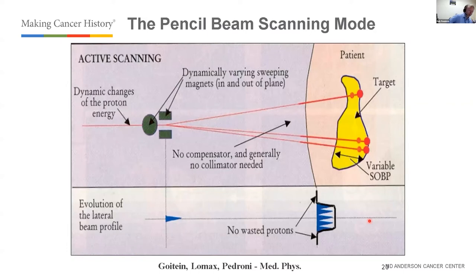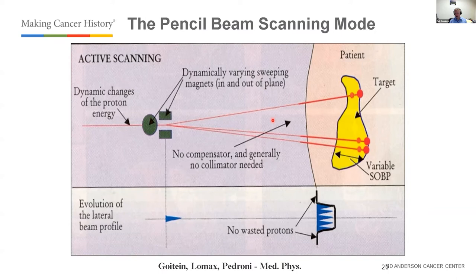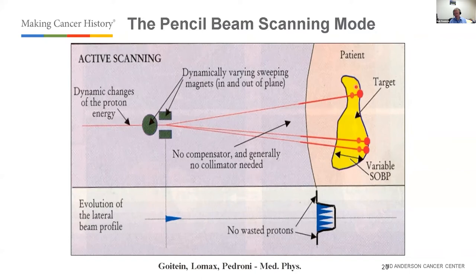For scanning beam, as shown in the Goitin and Lomax publication, two scanning magnets deflect the beam to desired lateral positions. The beam is delivered at the correct energy directly from the accelerator for each depth layer, with no patient-specific hardware blocking it — hence essentially no wasted protons, compared to the factor of 30 waste in passive scattering. You deliver the deepest energy layer first, then progressively lower energies, painting a 3D dose volume with individual spots.